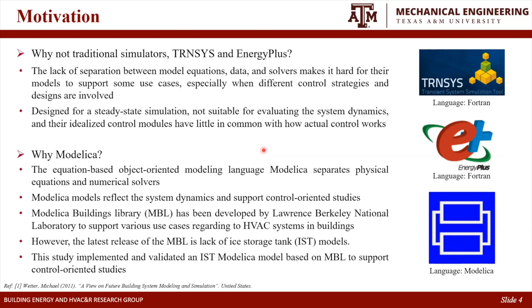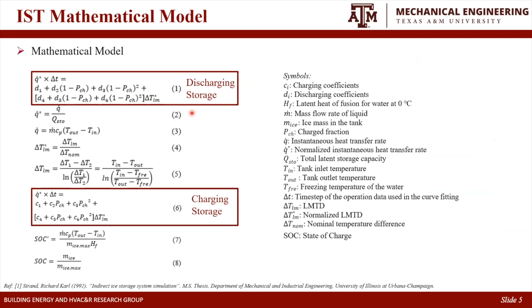We need the mathematical model. We use mathematical equations based on the reference. For example, the discharging rate and charging rate are based on curve-fitting data. And the most important part in this mathematical model is that we are using the log mean temperature difference — that is equation 5 — to calculate the outlet temperature when we have the inlet temperature and mass flow rate. And when you calculate the outlet temperature, you can calculate the state of charge using equations 7 and 8.